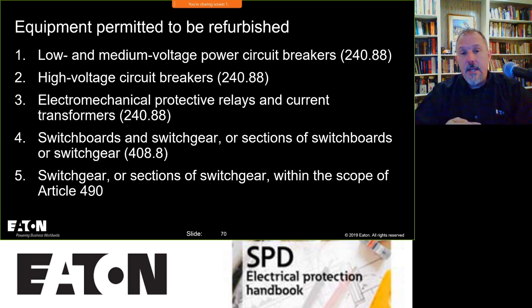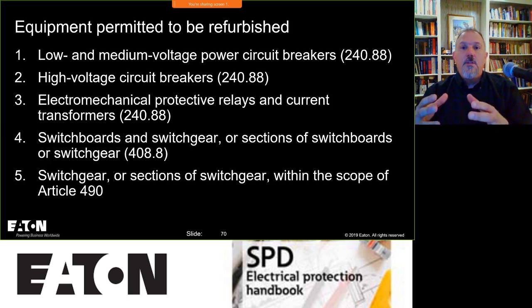And my response to that is that it says there's nothing in there that says you can't. So if the code is silent on it, that means you don't have anything in the NEC that says you can't do something. So if you have a motor, or something like a safety disconnect switch, I don't believe safety disconnect switches are in here anywhere. If you don't have language in the National Electrical Code that says you cannot refurbish or recondition something, then there's no prohibition on it.